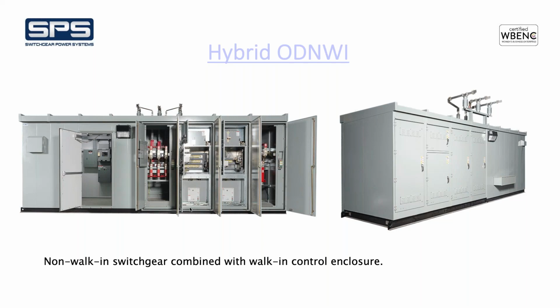and then the breakers and switches are non-walk-in. I mentioned roof bushings earlier, so this is obviously an example of that, where this customer is able to come right off the secondary of their transformer in the substation and connect right to the spade connectors, and they connect down into the switchgear. So it's a very clean design and easy design to implement in the substation.